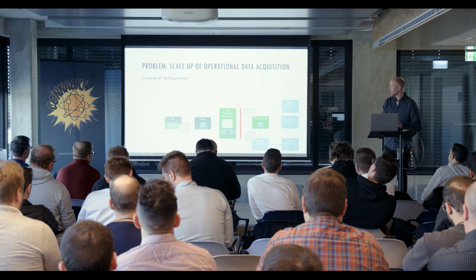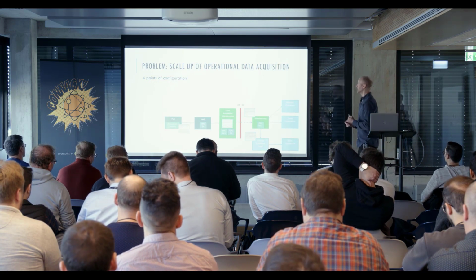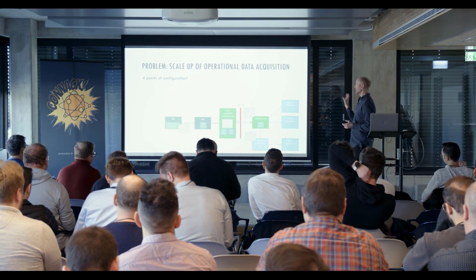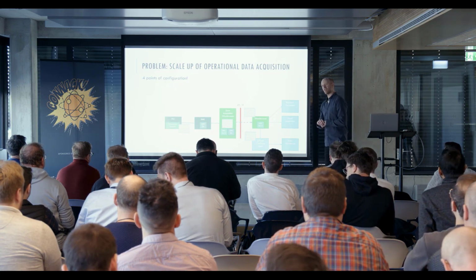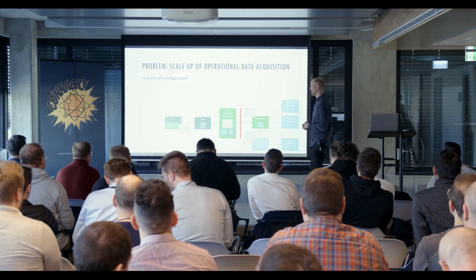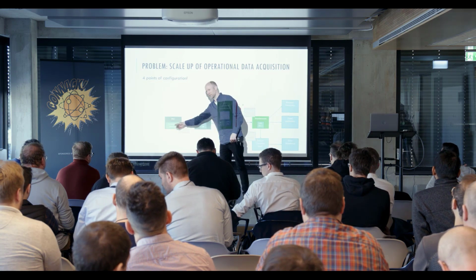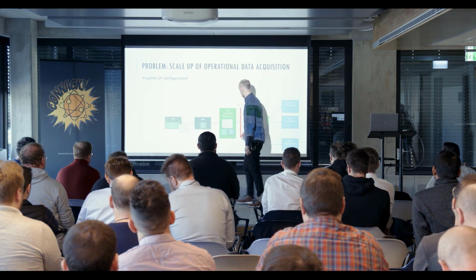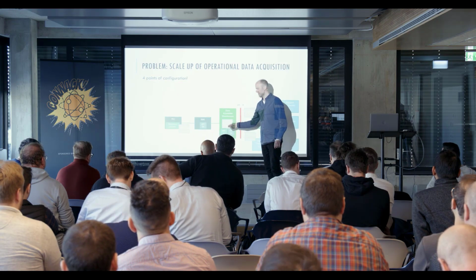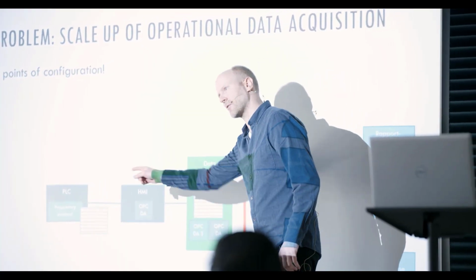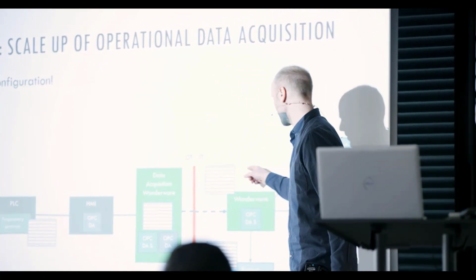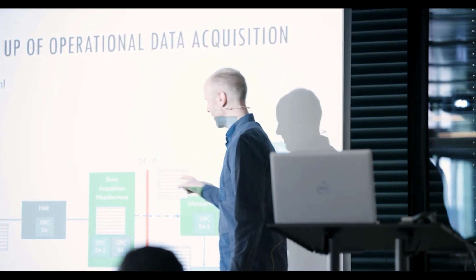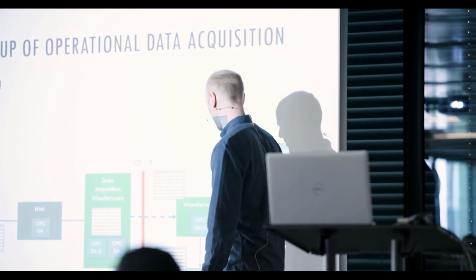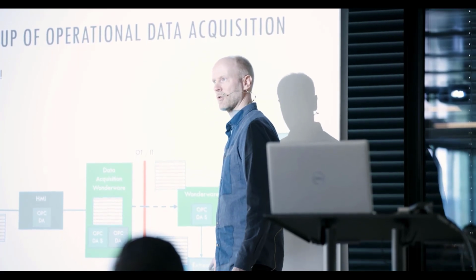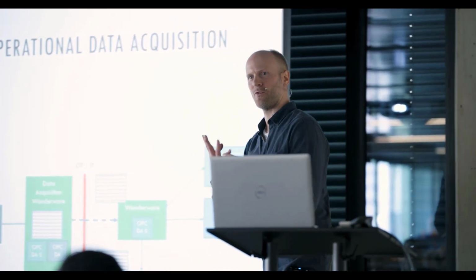So back to our problem, and those signal lists - we used to have 4 points of configuration in our system. We needed to expose this on the PLC, set up this gateway communication and assign a PLC address, do the same in Wonderware and know the gateway address, and then also do that for the extract transform load. So you had 4 places to configure for every new data point.